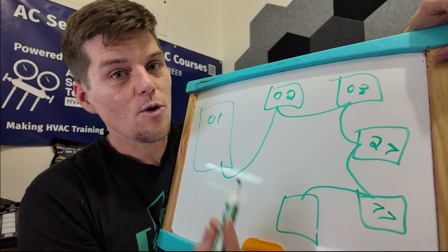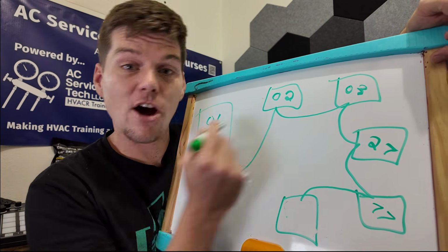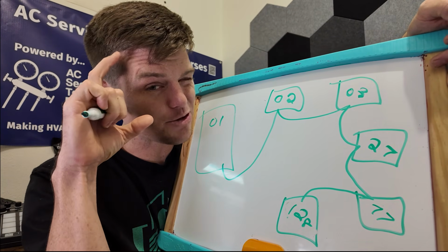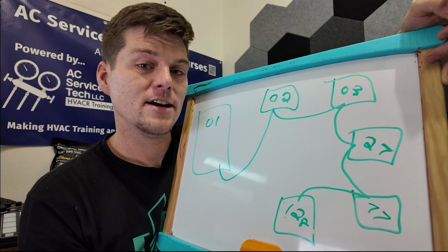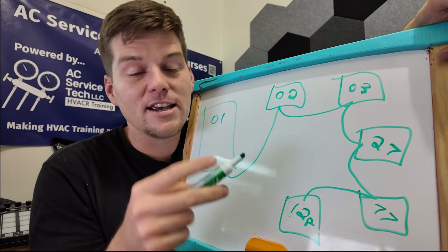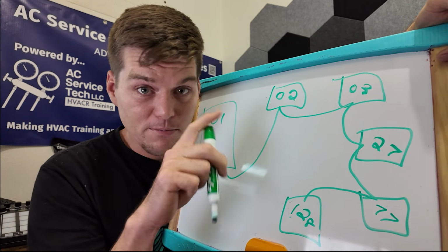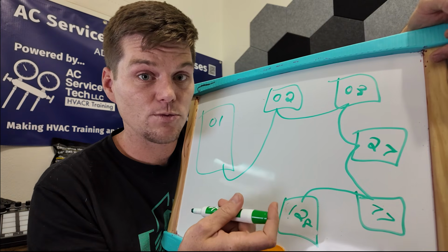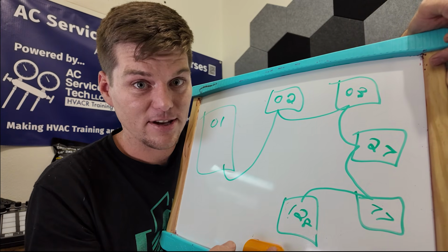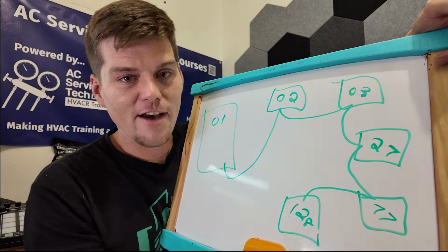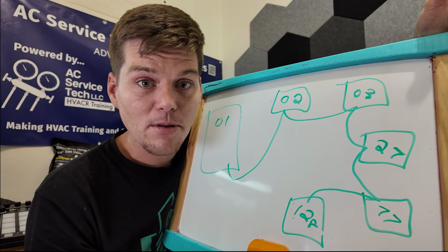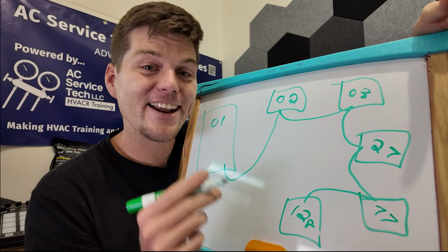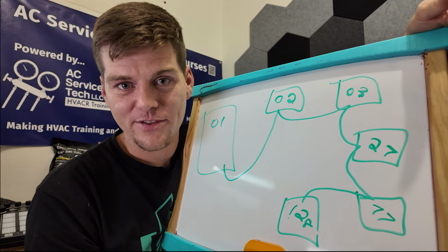So what do we do then? We can count indoor units. But remember, when we do the auto address on this system, the system itself is taking a snapshot, a photo of how many indoor units it has. And so if you go in and you say, well, Roman, it's just as easy as actually typing in a few, setting modes here and counting how many indoor units there are. Well, you forget that the count of the indoor units is what was taken during the auto address sequence. And so it's going to say that it has 5 indoor units. And you're going to say, well, what the hell's the problem then? You see 5 indoor units. There is 5 indoor units. Let's go. And that's not a correct solution. That's not even accurate at this point.